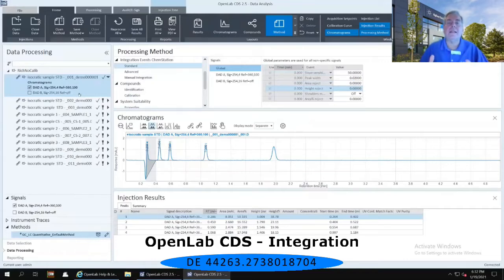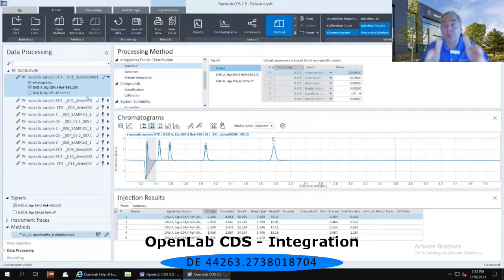So I immediately start lowering the slope sensitivity — from 50 down to 20 instead. Once again, I right-mouse click on that one injection on the left-hand side and reprocess that selected injection. Sure enough, lowering the slope sensitivity from 50 down to 20 immediately gets me my much broader peak — the last peak at 1.975 minutes.